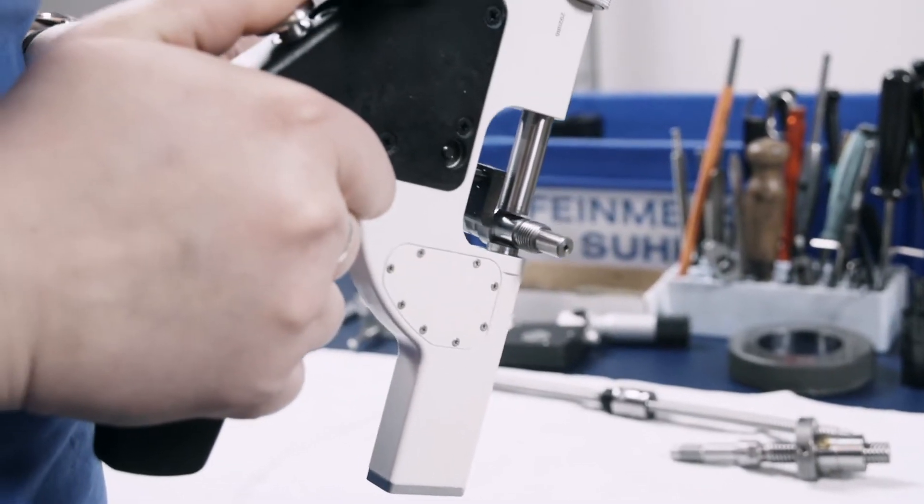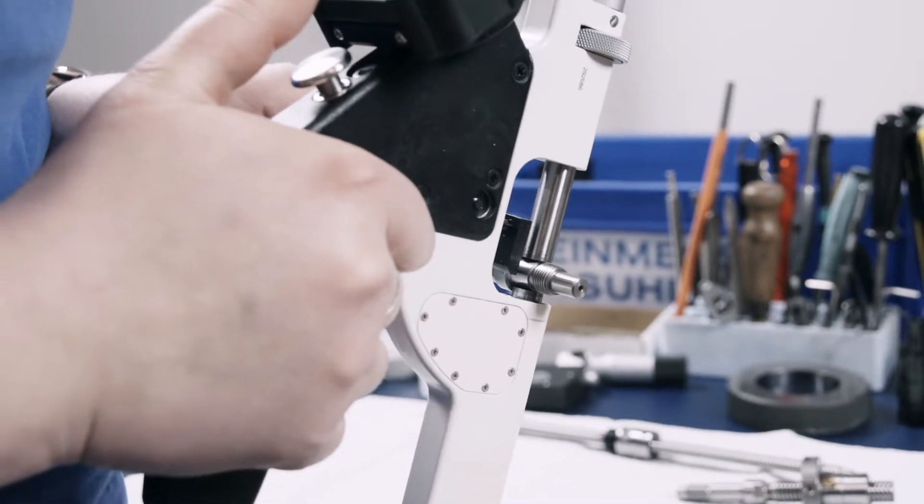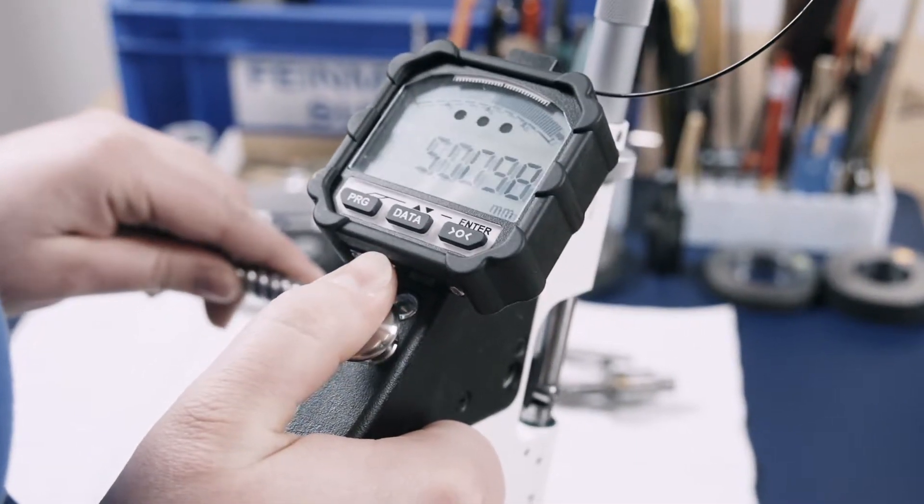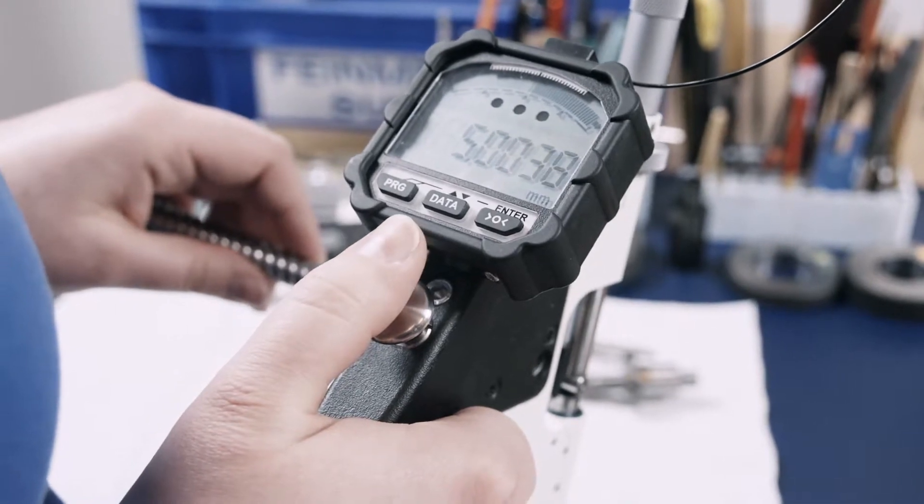Thus guaranteeing a repeat accuracy of less than 0.3 micrometer through a constant measuring force of 12 to 18 newton.